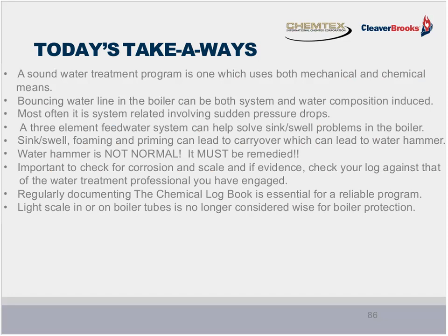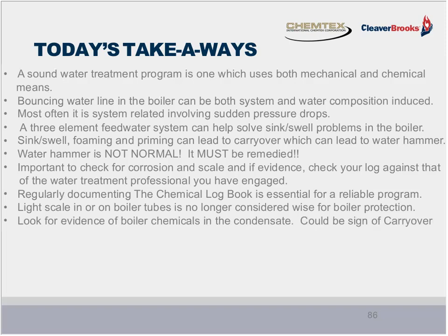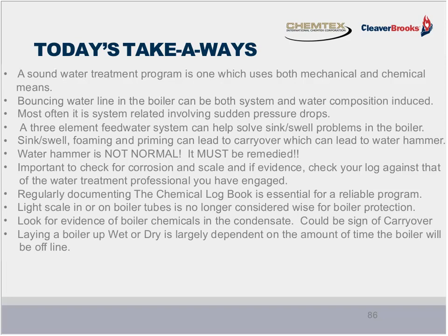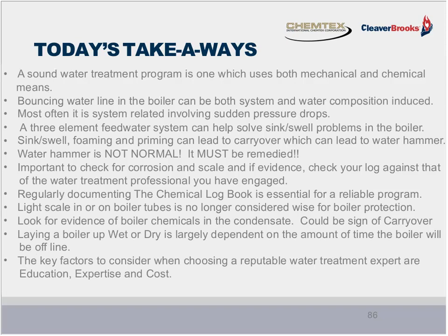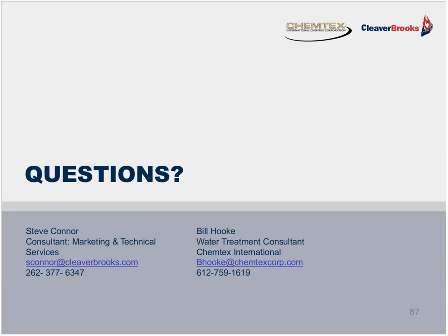Light scale in or on the boiler tubes is no longer considered wise for boiler protection. Cost of fuel is just too much. Look for evidence of boiler chemicals in the condensate. It could be a sign of carryover. Laying a boiler up wet or dry is largely dependent on the amount of time the boiler will be offline. And the key factors to consider when choosing a reputable water treatment expert are education, expertise, and cost. And now it's time for some questions.